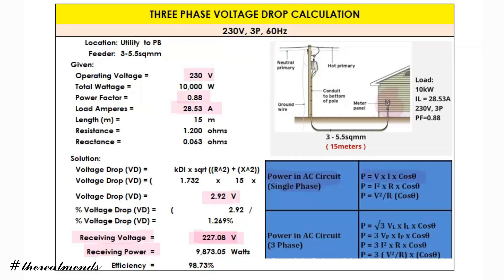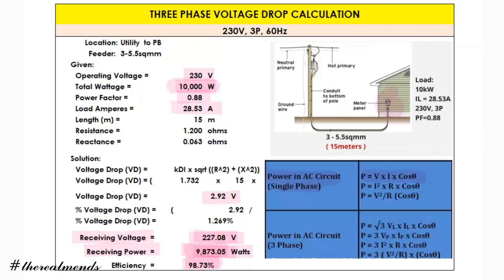The voltage is 227.08, multiplied by the current of 28.53 amperes times the power factor of 0.88, giving an answer of 9,873.05 watts. To get the efficiency, divide the power output of 9,873.05 by 10,000. The power efficiency is 98.73 percent. The receiving power is less than 10 kilowatts because of the 2.92 volt drop — meaning when there is a voltage drop, there are also power losses.